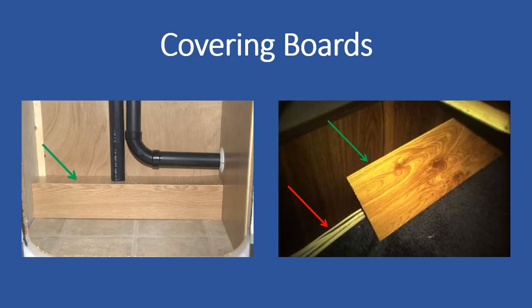Typically, the term covering board has been associated with strips of wood used to cover exposed Romex. As seen in the figure on the left, the covering boards cover the Romex completely. However, the figure on the right shows the covering board only covering the Romex partially, leaving some exposed, unprotected wire shown by the red arrow.